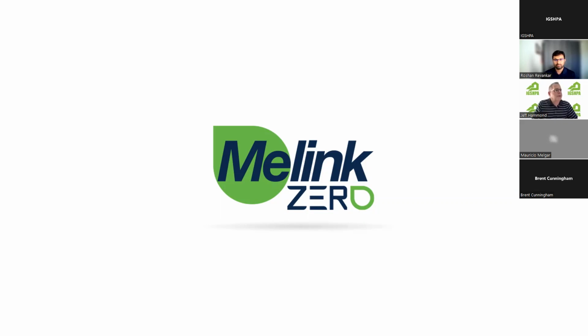Thank you, Roshan. Greg asks, what is the phase change material with a melt point of 70 degrees? What sorts of PCMs have you evaluated, and which pair well with ambient loops? One of the things we did in trying to get to that 70-degree PCM mark was work with the best minds in the industry, including top-notch professors at Oak Ridge. There is no cost-effective PCM in the world that can do 65 to 75 degree phase change. We initially evaluated organic PCMs just to confirm it could be done, but those were really expensive. We wanted to get our cost below $500 per ton-hour capacity, first cost, so that was our target.